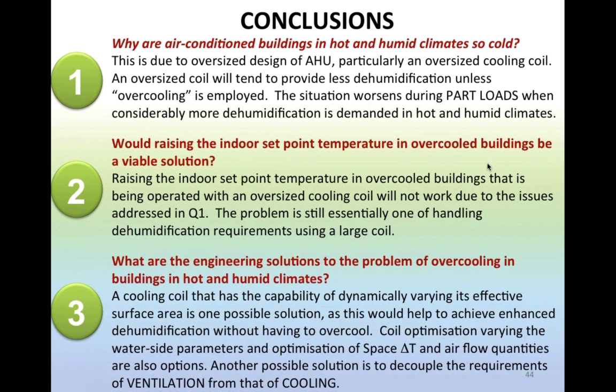But the main challenge with cooling coil is any increased capacity or any oversize that we build into the system goes against the basic consideration of the correct surface area requirement for the latent cooling load handling. In other words, we need to work with the fact that you're going to have an oversized coil. How can we then make it adaptable when we have varying cooling loads? So even if you have a peak design that is correctly designed and estimated, when it gets into a part load stage, we do have that mismatch between what the coil was selected for and what the actual cooling load is in terms of the part load.